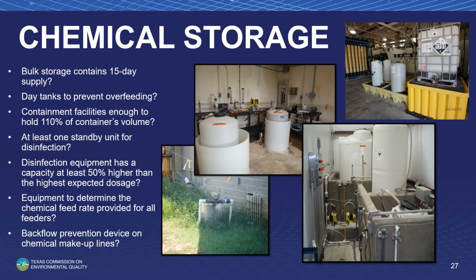Speaking of chemicals, chemical storage. So bulk storage, do y'all have at least a 15-day supply of chemicals on site for your plant? Do y'all have day tanks to prevent overfeeding of chemicals? And the biggest one that we find at surface water plants is, do you have secondary containment for all of your liquid chemicals? And can it hold up to 110% of your typical amount of liquid chemical that you'll have there? As you can see here, there's a variety of ways that you can achieve this. Cutting an old chemical tote in half from a bigger chemical and then putting your smaller tank in there, that can work as long as it holds 110%.